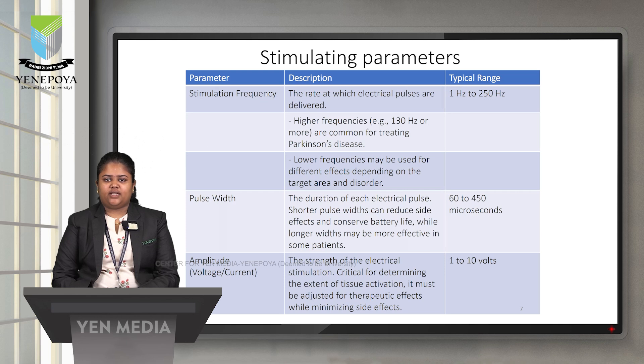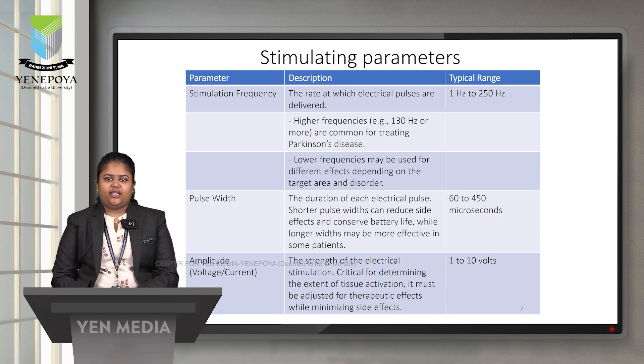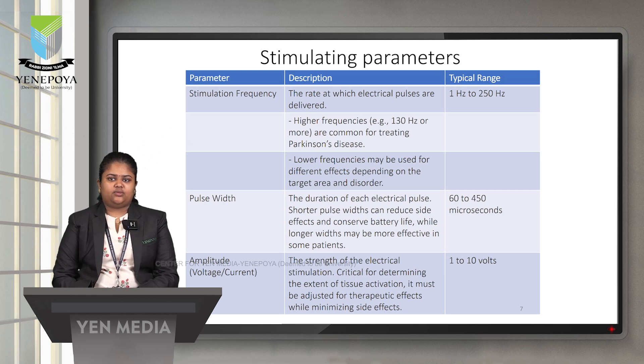The stimulation parameters in DBS include: stimulation frequency — the rate at which electrical pulses are delivered; higher frequencies are used for Parkinson's disease while lower frequencies are used for different effects depending on the target area or disorder, with a typical range of 1 Hz to 250 Hz. Pulse width is the duration of each electrical impulse; shorter pulse widths can reduce side effects and extend battery life, with a typical range of 60 to 450 microseconds. Amplitude refers to the voltage or current strength of the electrical stimulation, critical for determining the extent of tissue activation, with a typical range of 1 to 10 volts.